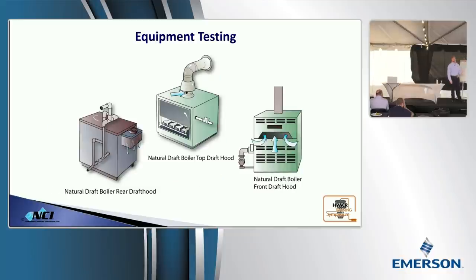Now you'll notice that there's no illustrations up here of condensing equipment. And that's because by definition, when you've looked at all the causes that we're talking about, you can't have a combustion air problem on condensing equipment. Those of you that work on equipment a lot for 90%ers, what's the typical pressure switch rated at? Like an inch, isn't it? Over an inch? Those little inducers are strong. They're very strong. As we talk about combustion air, it takes natural building pressures or a fan to interfere with them. Very rarely will you ever encounter that on 90% equipment. It'll always be natural drafts or more commonly Category 1 equipment if you're looking at it by code definition.